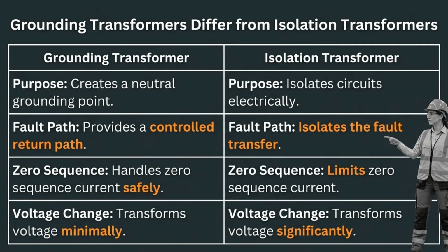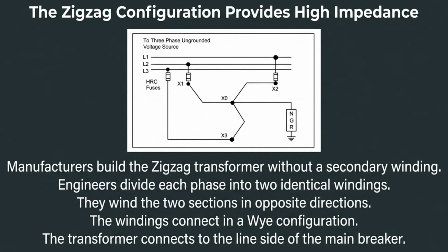It is important to distinguish between grounding and isolation transformers. While isolation transformers electrically separate circuits, a grounding transformer is specifically designed to create a neutral point and manage fault current safely with minimal voltage transformation. The Zig-Zag configuration is a common choice for grounding transformers.